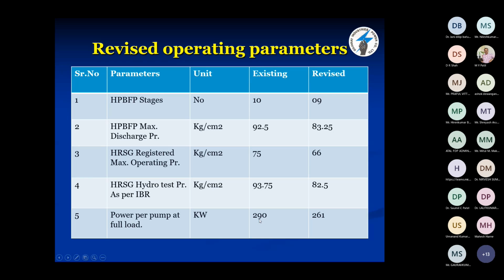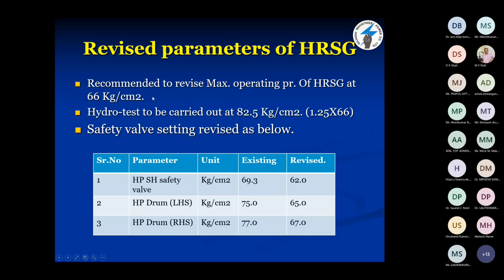Power per pump at full load was 290 kilowatt, and now it will be 261 kilowatt. It was recommended to revise the maximum operating pressure of HRSG to 66 kg, and accordingly all the safety valve settings will also be revised, because earlier they were for higher pressure, and we cannot go beyond 66 kg. So we have revised the safety valve setting. Earlier it was 69.3, now we have revised it to 62 kg. Accordingly, for HP superheater and drum, all the safety valves are revised from existing 75 to 65, and 77 to 67.